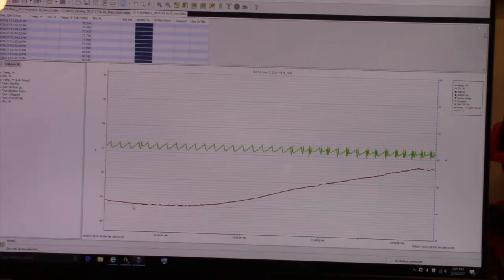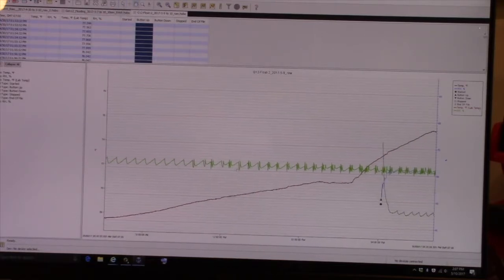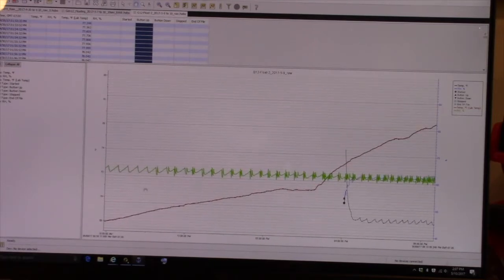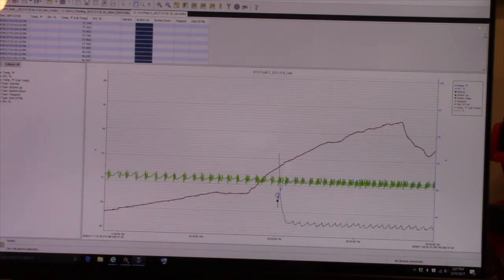This is the ambient. And you can see that what I'm doing is I'm just bopping right around here between, say, 60 and 63 RH. Most of the time between 61 and 62 RH, right around in this area, okay? And this is performance down in the 60s. And as we move across the chart, the important thing is that what you're not seeing are these types of long strings where you have pronounced dips in relative humidity, and you also don't see huge variations in temperature.